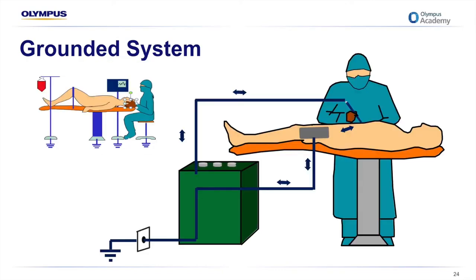A grounded system is happy for current to go to ground. Any ground. That could be even through the metal pole, which may or may not be in contact with the patient. There is no mechanism to measure leaking. This is not Australian standard. This slide depicts a grounded generator. This type of generator significantly increases the patient's risk of burn injury at the return electrode site or alternate pathway sites. With this type of generator, the current is referenced to ground, which leads to the possibility of burns at the return electrode site as well as alternate pathway sites because of current diversion.